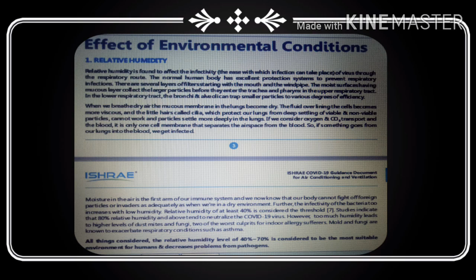Relative humidity of at least 40% is considered the threshold. Studies indicate that 80% relative humidity and above tend to neutralize the COVID-19 virus. However, too much humidity leads to a higher level of dust mites and fungi. Two of the worst culprits for indoor allergy sufferers, mold and fungi, are known to exacerbate respiratory conditions such as asthma. Considering all this, a relative humidity level of 40 to 60% is considered the most suitable environment for humans and decreases the problems from pathogens.